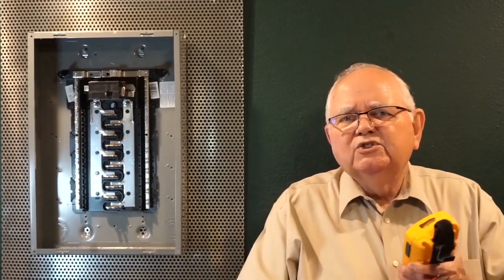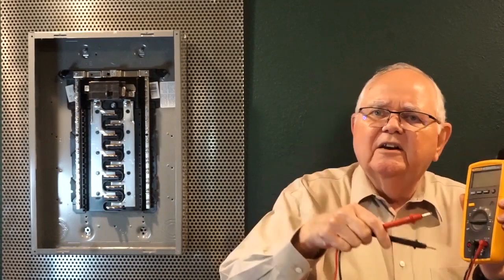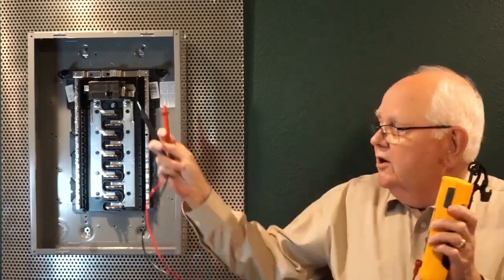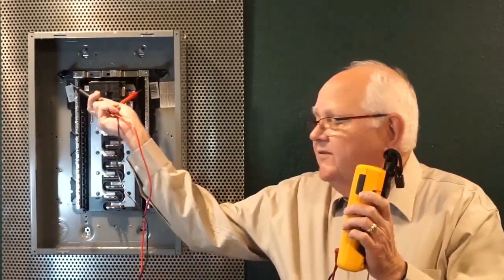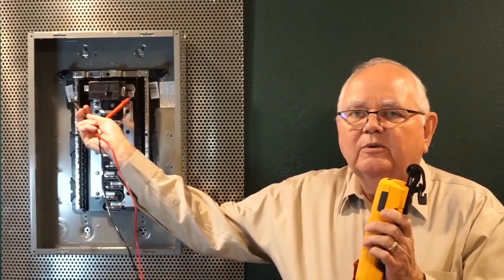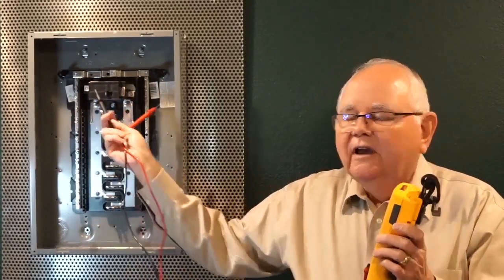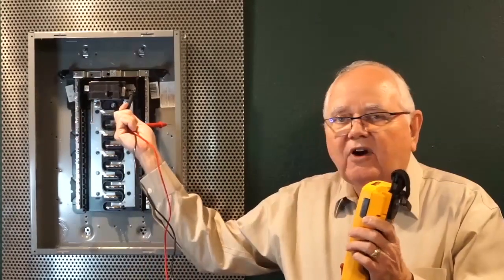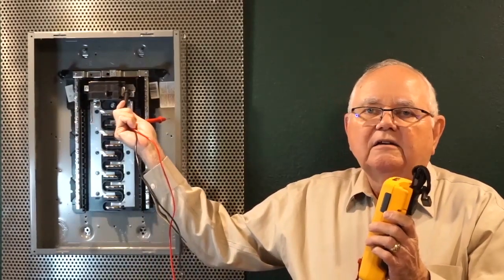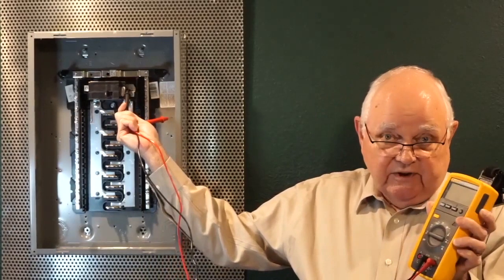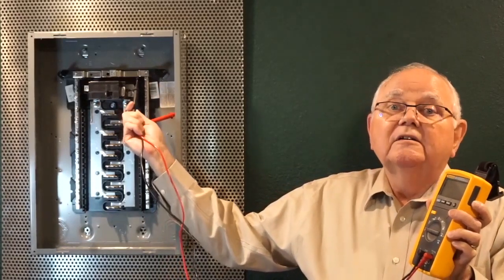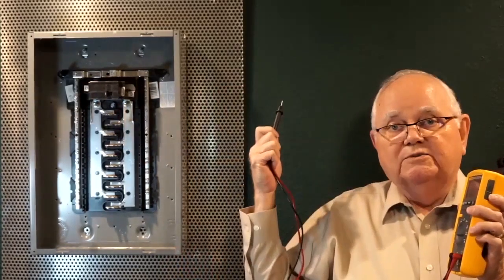We want to first make sure our meter works properly by checking it on a known voltage. Then we want to go in and verify from phase to phase across those incoming terminals where the power comes in. And then we want to check from each phase to ground and make sure that we have 0 volts on our meter. Then we want to make sure our meter still works properly. So it's a 3-point method.